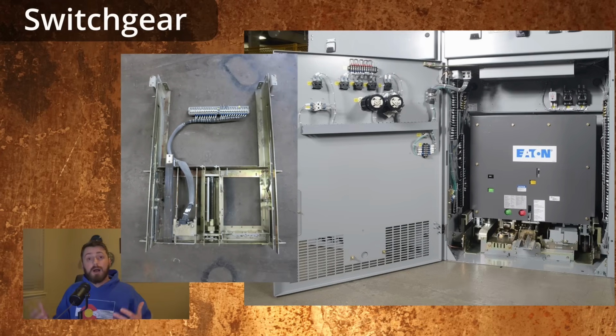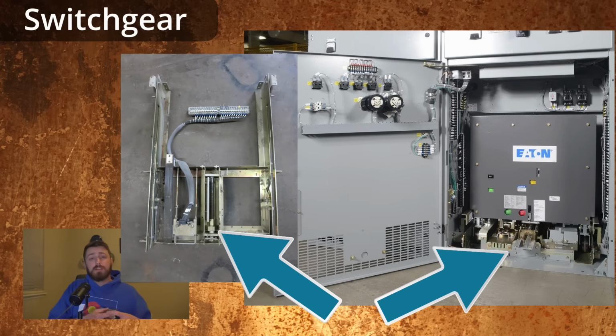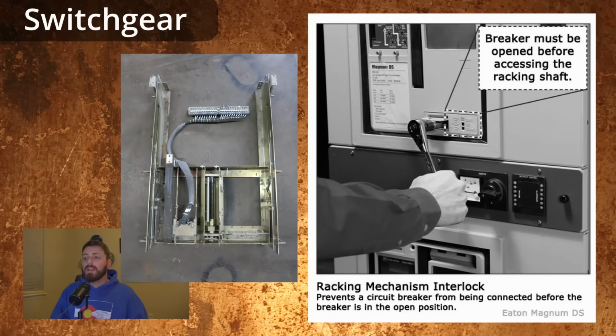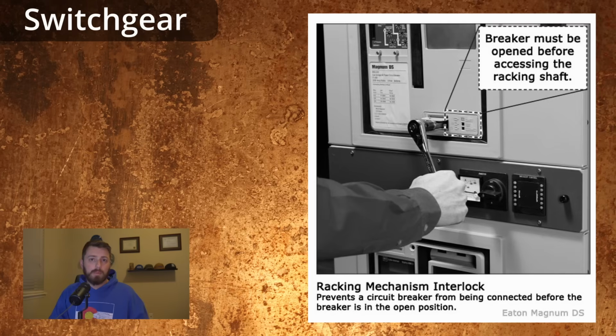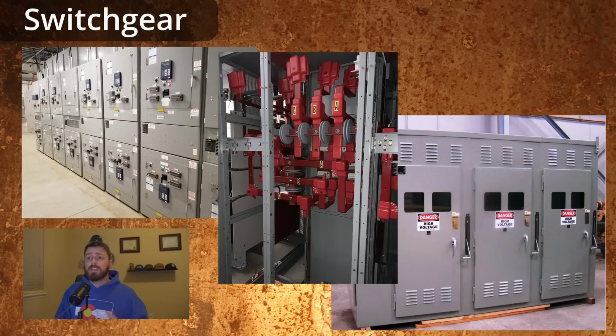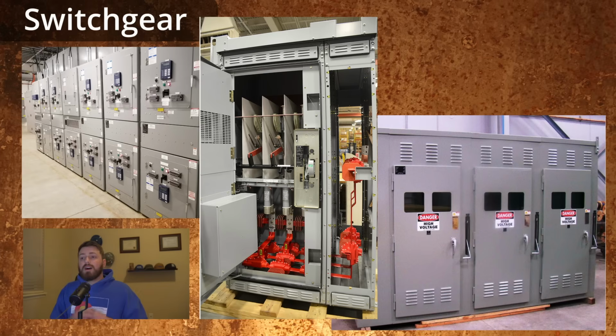Due to the large size of switchgear assemblies and the breakers inside them, it's common to find what we call draw-out circuit breakers that can easily be removed from energized bus using a racking mechanism. It's like a draw screw at the bottom that pulls the breaker off of the bus instead of having to shut the whole board down and directly unbolt the breaker from the bus, as we see most typically in switchboards and panel boards. I'll put some examples of medium voltage switchgear up too, as well as switchgear containing manual fuse disconnect switches. All of these would be considered switchgear and not switchboards.